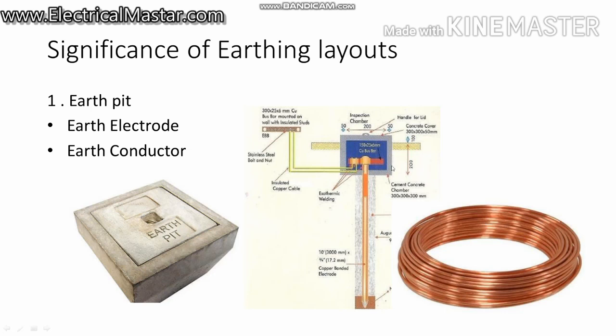You can see in this picture, this is the earth pit. Inside, we are connecting the earth rod. We dig this earth rod a minimum of 3.5 meters into the ground. From the top side of the earth rod, we connect the earth cable to the earth bus bar.